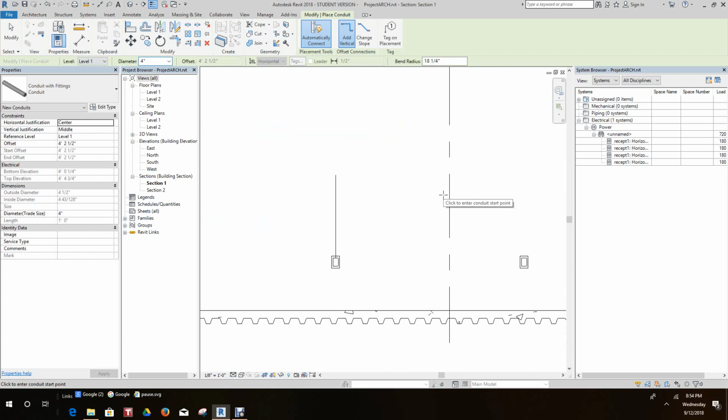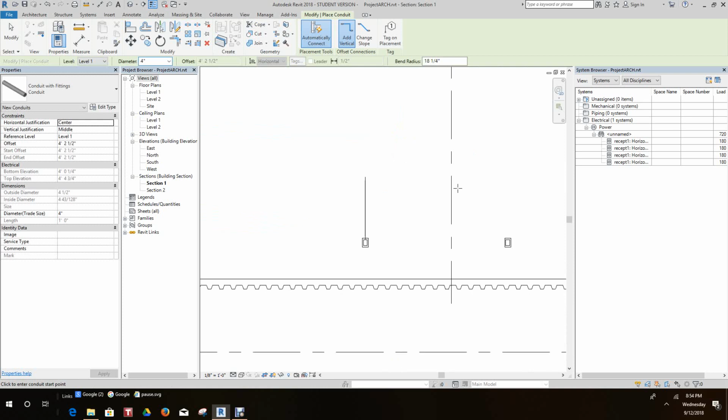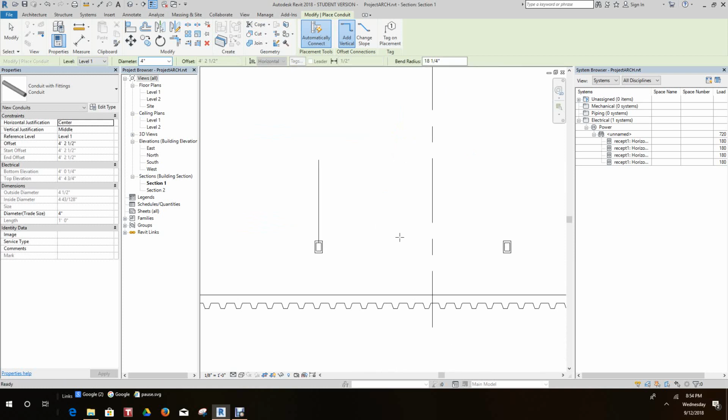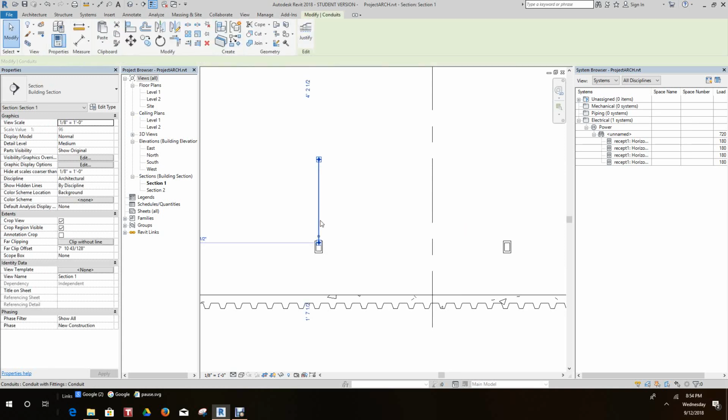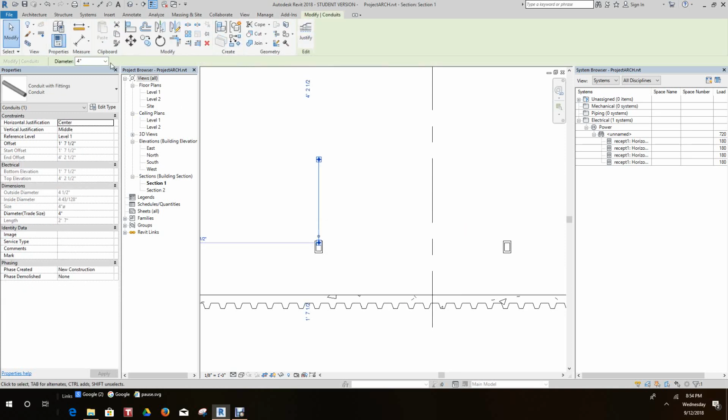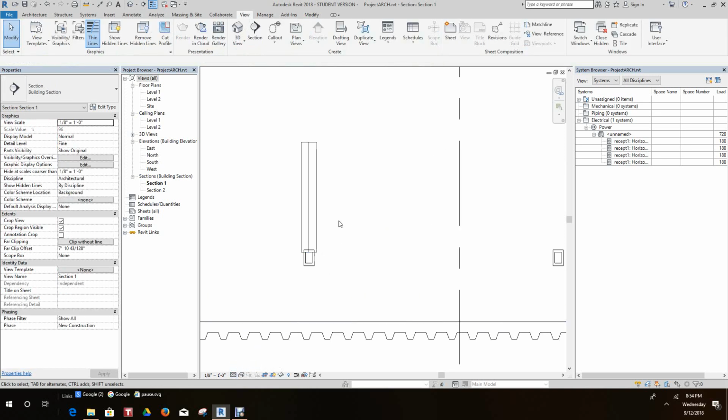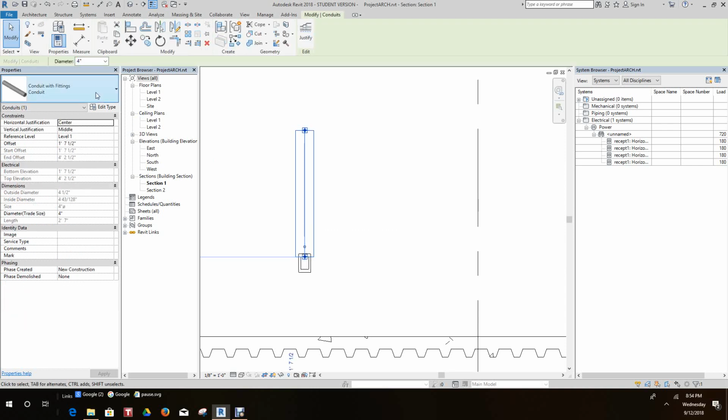Now, you want to go along here. Now, I think what's happening here, okay, the conduit is too, let me see what happens here. Let's go to find, see that conduit is too big, so I need to drop this down to 1 inch.